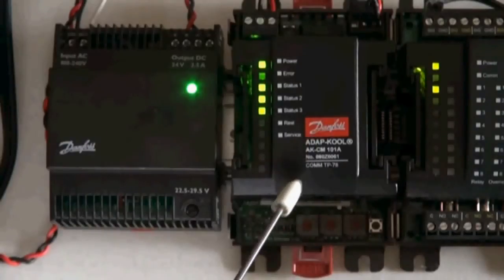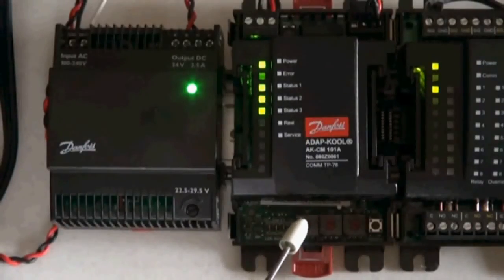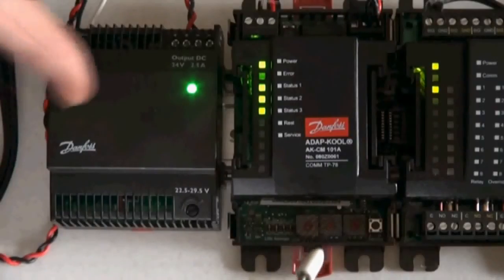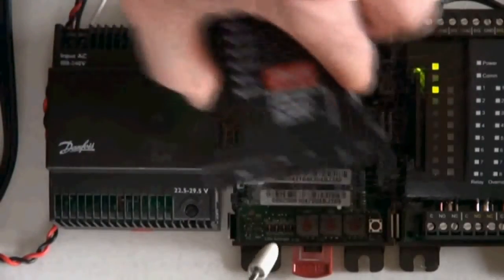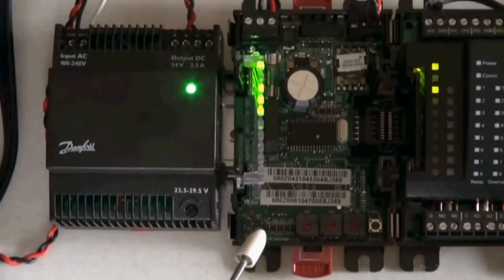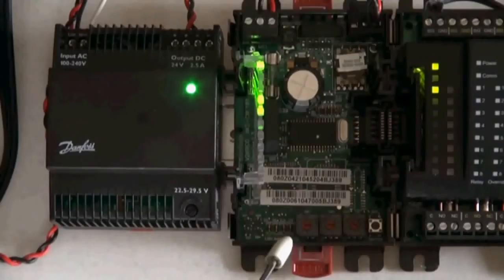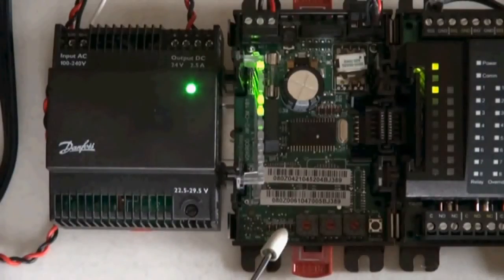The cover of this module and other modules can be removed by squeezing the right and left side and pulling toward you. This reveals the fuse inside the COM module and gives us a better look at the address switches. The address switches are important for setting up I/O points.